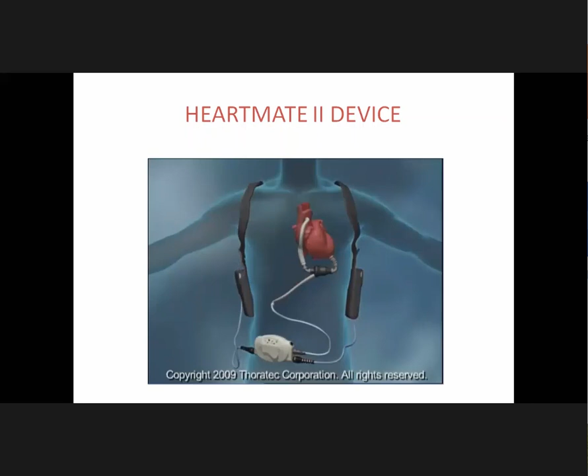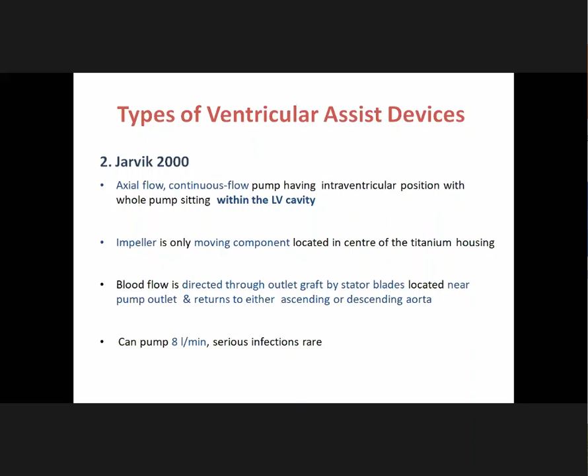Next one is the Jarvik 2000. It is an axial flow continuous flow pump having an intraventricular position with the whole pump sitting within the LV cavity. It has an impeller, which is the only moving component, located in the center of the titanium housing, and blood flow is directed through the outlet graft by stator blades located near the pump output and returns either to the ascending or the descending aorta. And it can pump around 8 liters per minute, and the chance of infections is very rare.